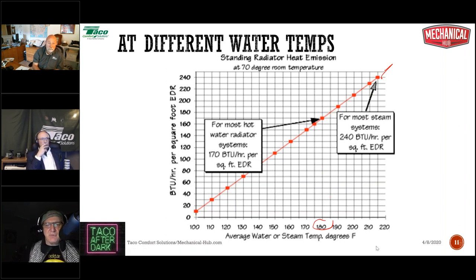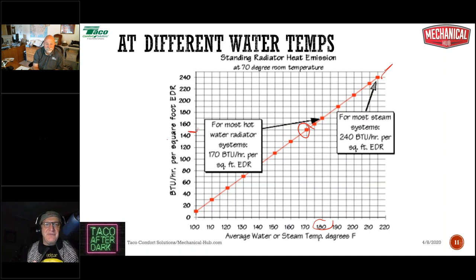I'm sorry, an average water temperature of 180. If our average water temperature was 170, if our supply was 170 and the average, let me try that one again, folks. It's late here too, and I've had that quarantini. At a supply water temperature of 180 and an average of 170, I have to now look right here for my output. Now my output is 100, and it looks like about 150 BTUs per square foot of EDR.